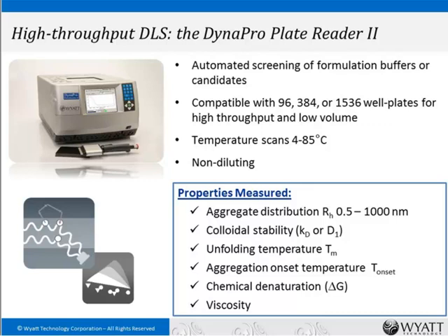The properties measured by dynamic light scattering include distribution of aggregates from 0.5 to up to 1,000 nanometers in radius, colloidal stability, unfolding temperature TM, and the temperature for onset of aggregation. You can also characterize chemical denaturation and the viscosity of your solution — which is important for highly concentrated proteins in order to assess injectability and processing.